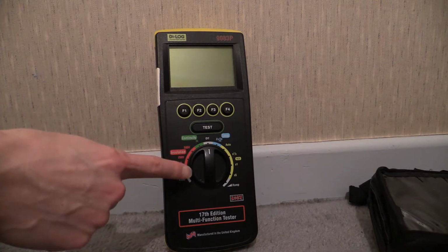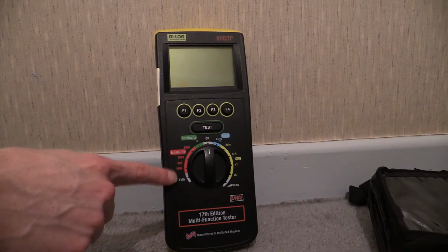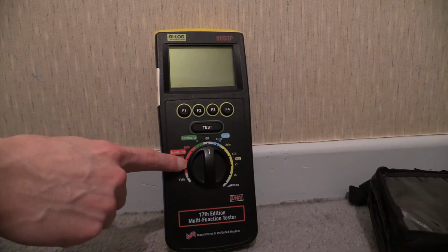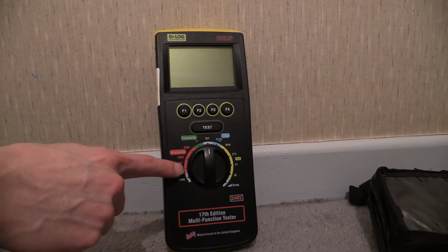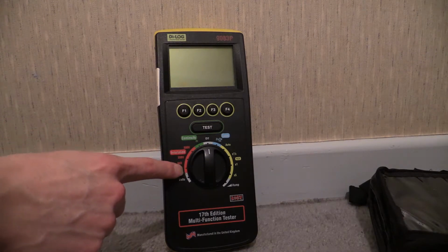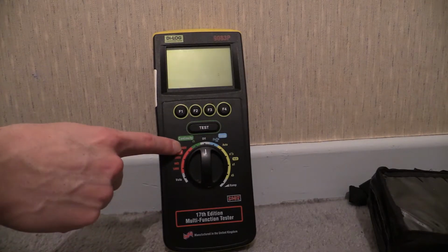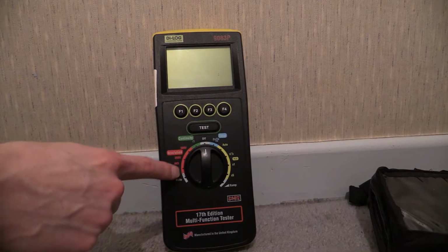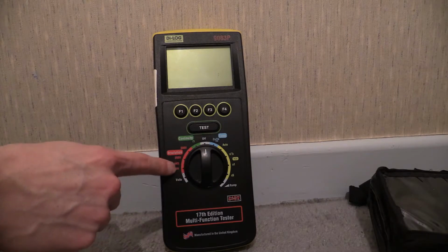Now on this one, for insulation resistance, it doesn't do the 1000 volt test. It'll be 100 volts, 250 volts, and 500 volts. You do get some models where it's 250, 500, and 1000 volts.